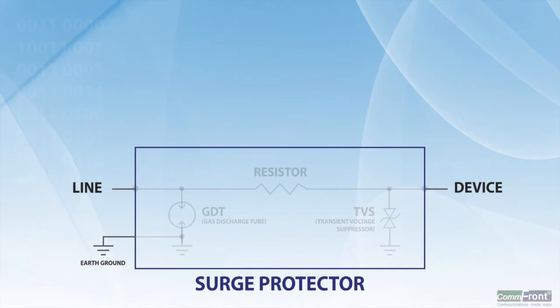Surge protectors are mainly used for protecting power and data lines against electrical surges and spikes, including those caused by lightning. The main function of a surge protector is to limit the voltage introduced to an electrical device by either blocking or shorting to ground any voltages above a safe threshold.